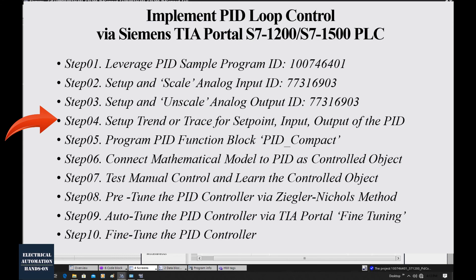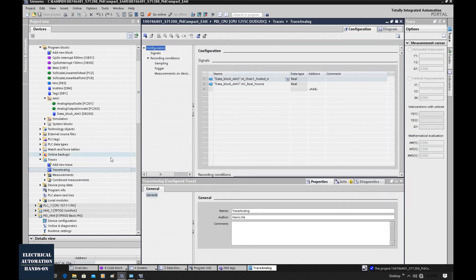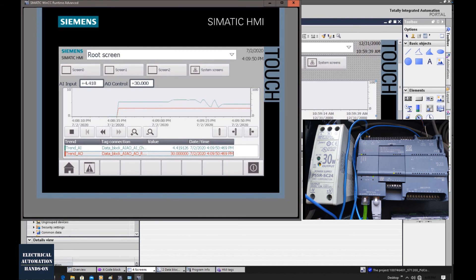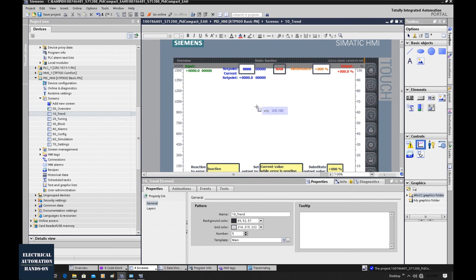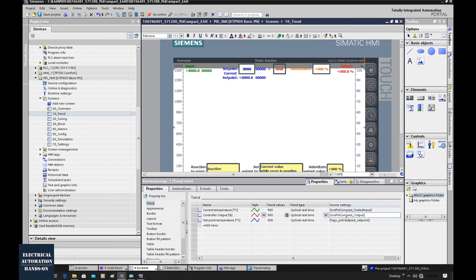That is step 4B: how we can set up the HMI trend. Comparing with the previous sub-step video, the trace function comes from the hardware itself, but the storage takes load memory from the controller. If you need to record a long curve, it is better to use the HMI trend function. Through this video, I showed how we can use the simulated HMI so that we do not need actual hardware. The simulated HMI can still communicate with the actual PLC controller, showing online data. You can quickly build up the trend and configure the three important values from the PID: setpoint, process feedback, and PID output.